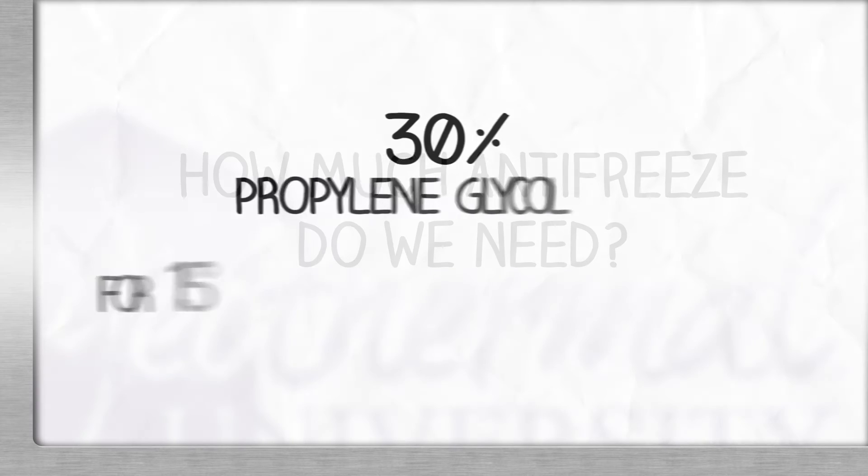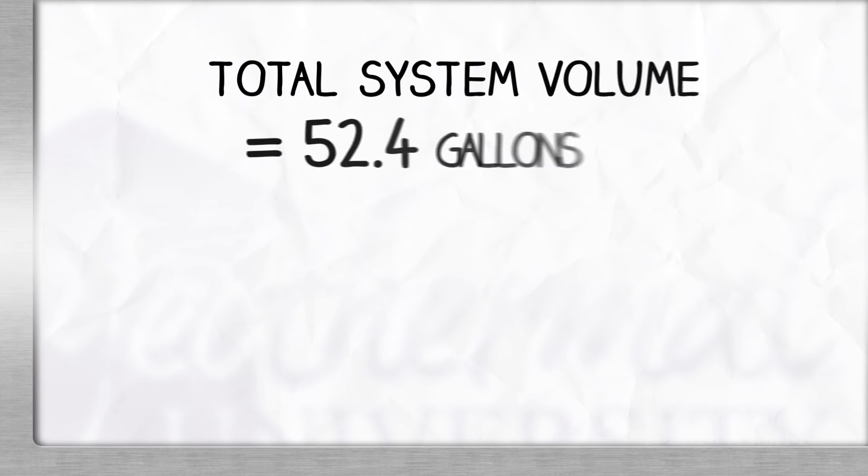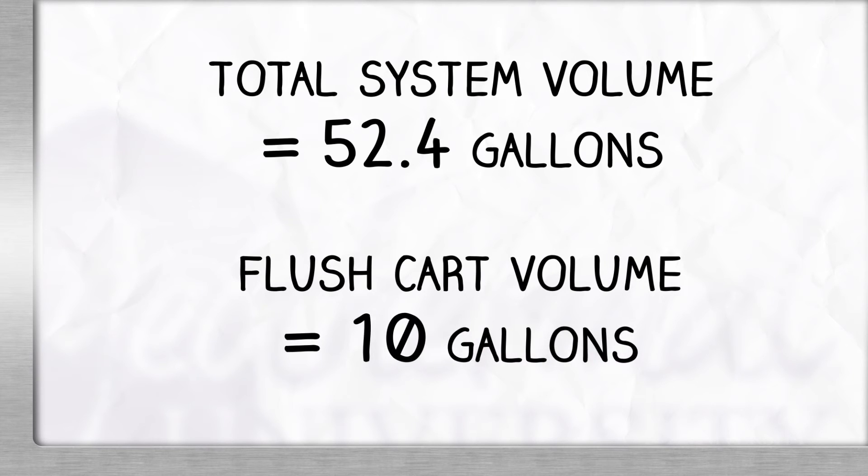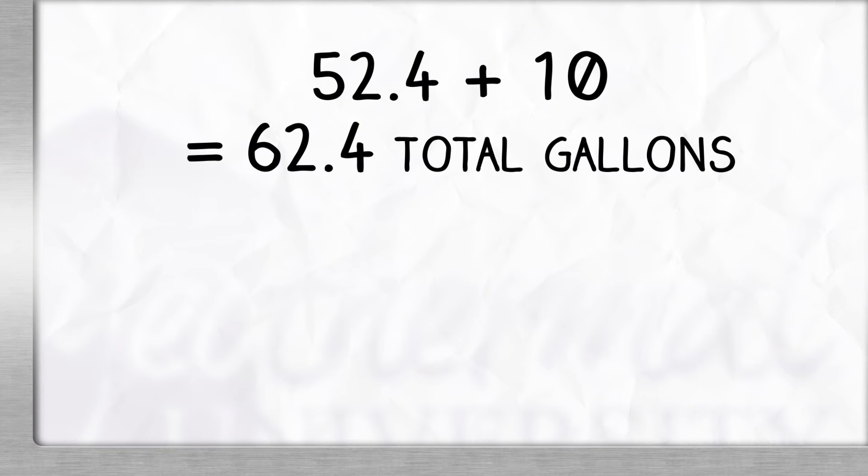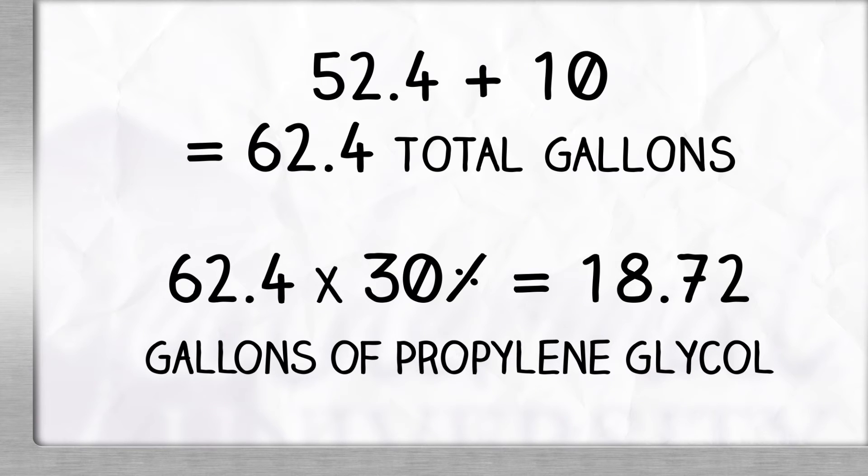So, how much antifreeze do we need? Vertical loops require 30% propylene glycol for 15 degree freeze protection. In our example, we have a total system volume of 52.4 gallons and a flush cart volume of 10 gallons. We added 52.4 system gallons plus 10 flush tank gallons to get a total of 62.4 gallons. We take our total gallons times 30% to get 18.72 gallons of propylene glycol.